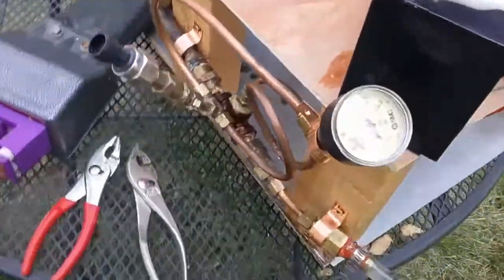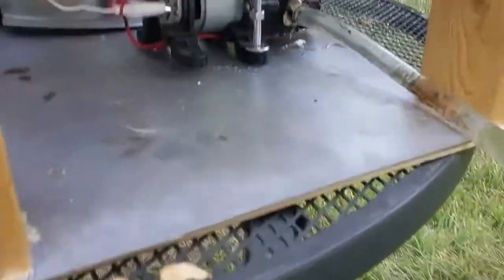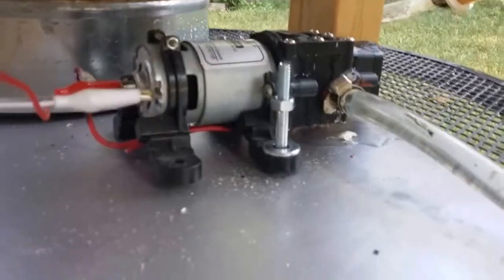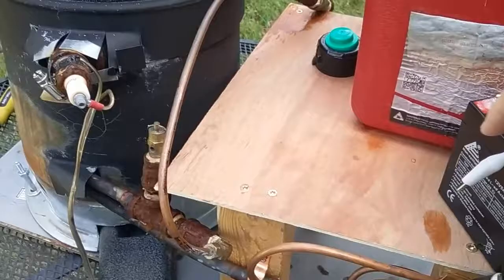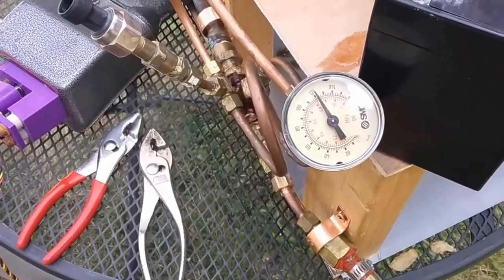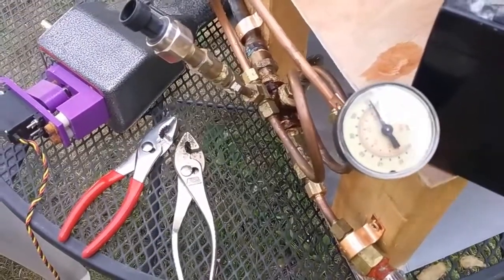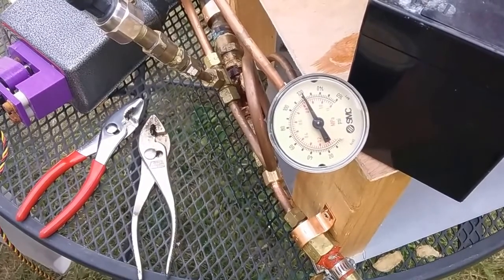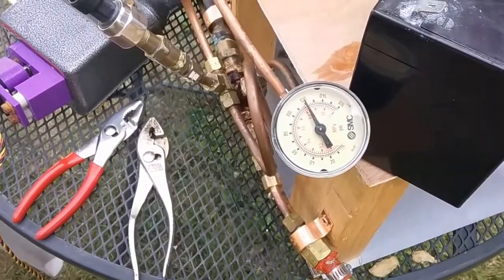You can see it's got a good 130 psi. The pump itself is leaking out the seams because that's about as high as the pump will go before it starts doing that. If we watch the pressure gauge, it seems like it's pretty good — very slow pressure loss, because some of these compression fittings are weeping a little bit. But I don't mind that.